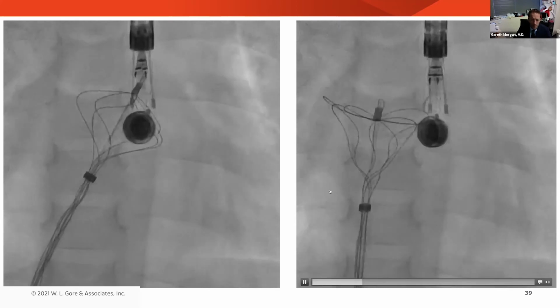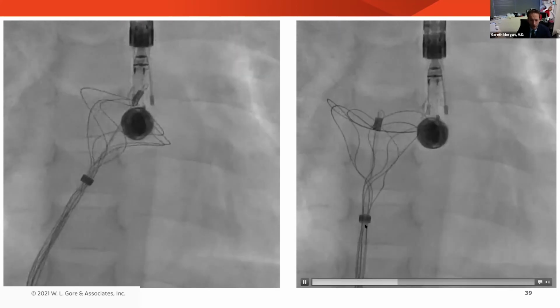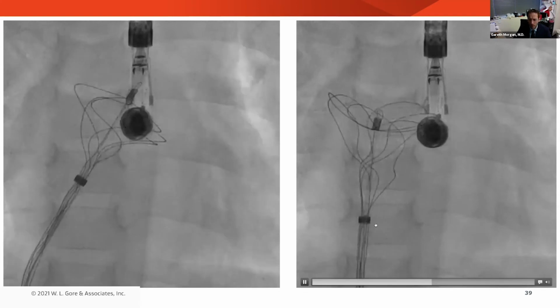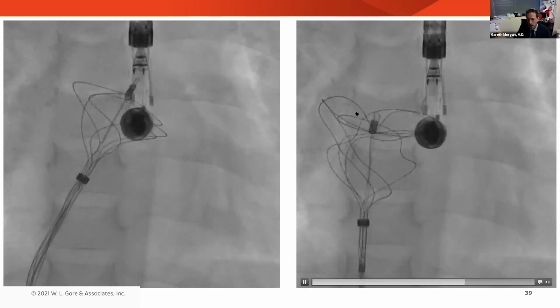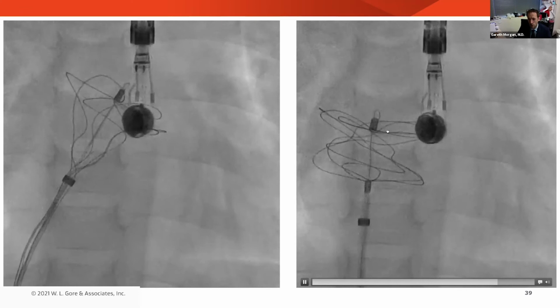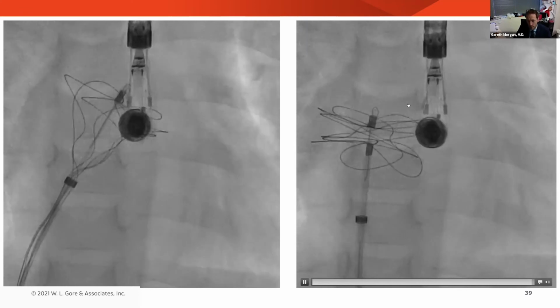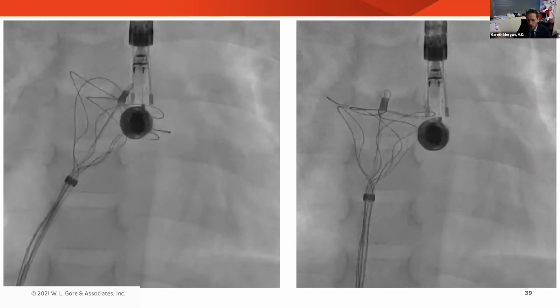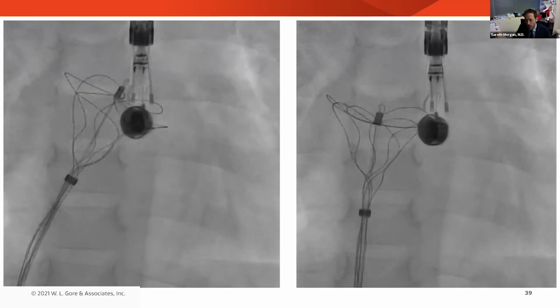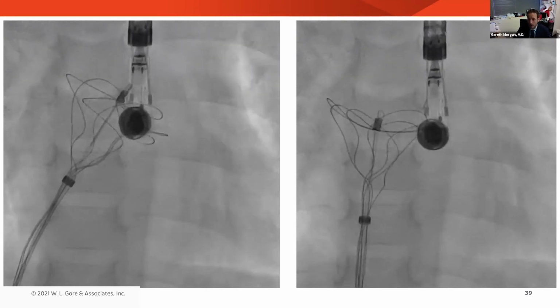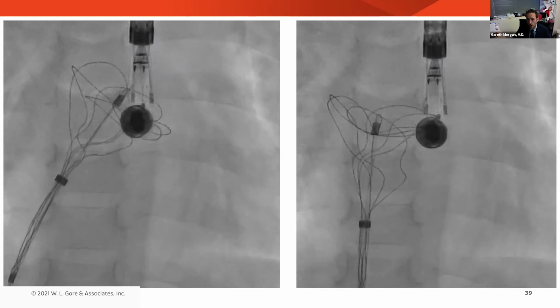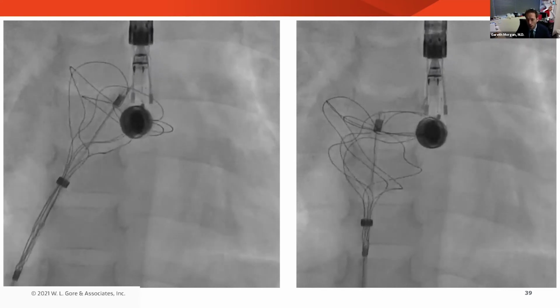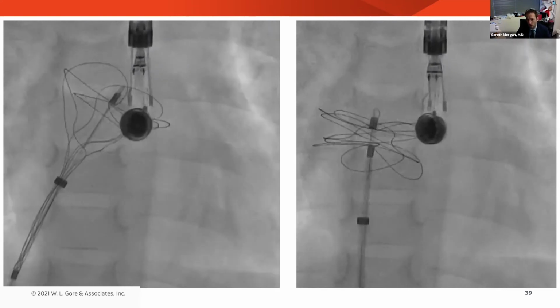Now on the other side, you can see several things. The orientation of the delivery catheter is quite different. And hence you end up with the ability to say that you could set a saucer on top of the left atrial disc of the device. And the reason is what I've done here is rotated the device between 90 and 180 degrees clockwise by rotating the entire handle.